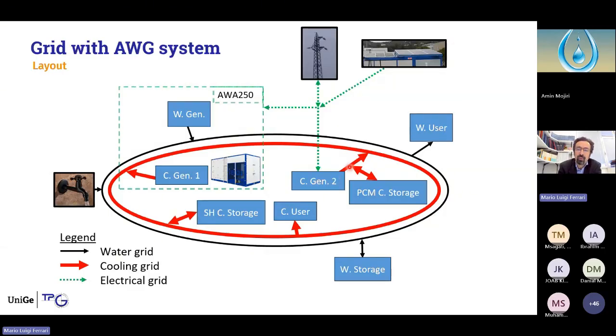This heat pump is also connected with phase change material storage for the cooling energy. Since this heat pump is able to produce the cooling energy for the cooling side at very low temperature conditions, in our test was down to -6 degrees C. It is possible to use simple water that is converted to ice as a phase changing materials that has been considered here. For sure, the cooling grid is connected with these systems here and here with devoted heat exchangers. The cooling grid is including also storage based on sensible heat that is the largest one that is able to generate good balance between generation and utilization in the grid.